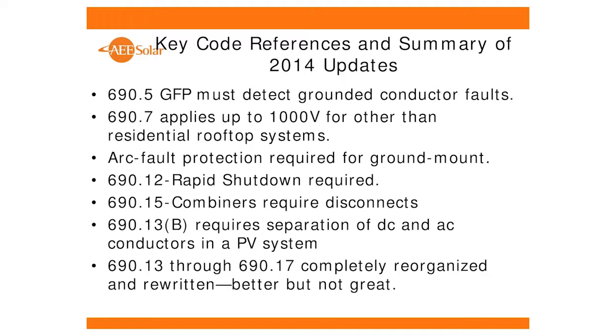the good news is that the industry has gone almost completely to what we call non-isolated inverters. Some people call them transformerless inverters. So most of the inverters you see out today are non-isolated inverters. They have very high resolution ground fault detection, and it detects ground faults on both positive and negative. So we're in really good shape with those products. The old products, fuse grounded inverters, are dogs, quite frankly, from a ground fault detection point of view, and they have some real issues.